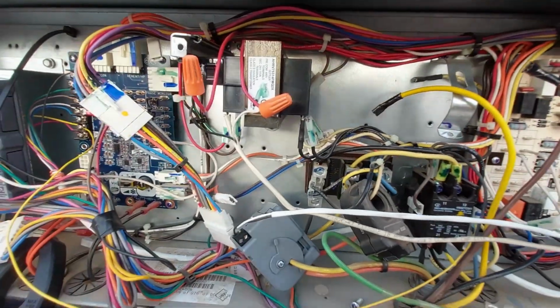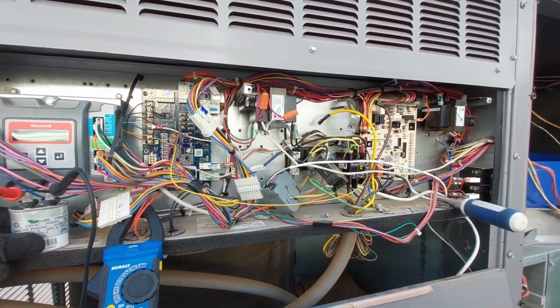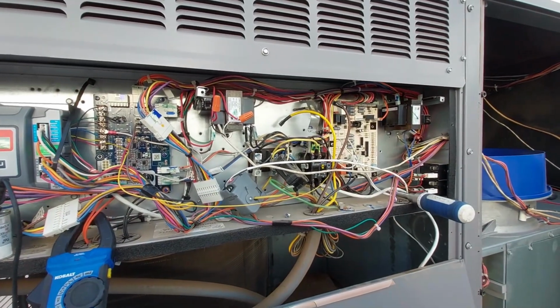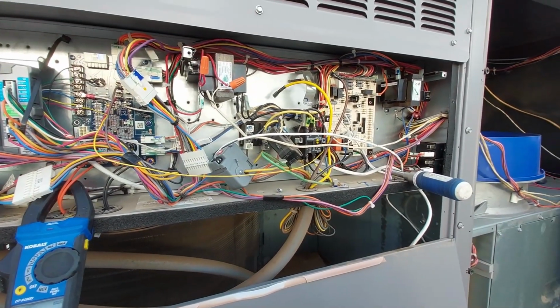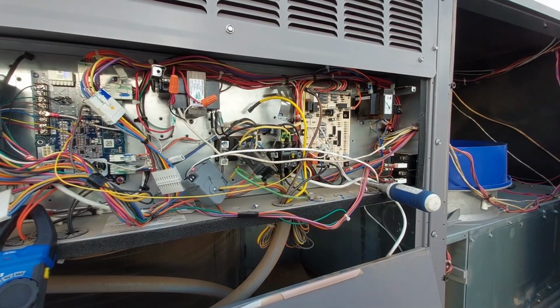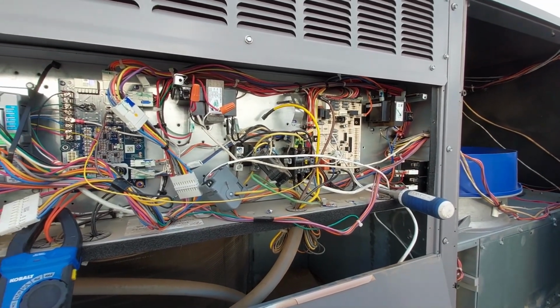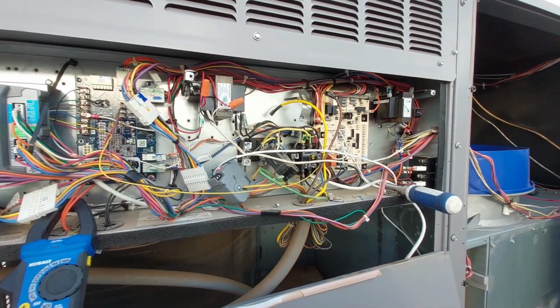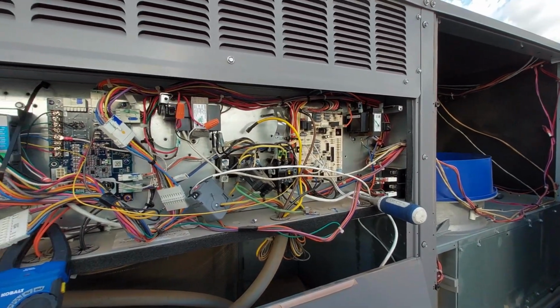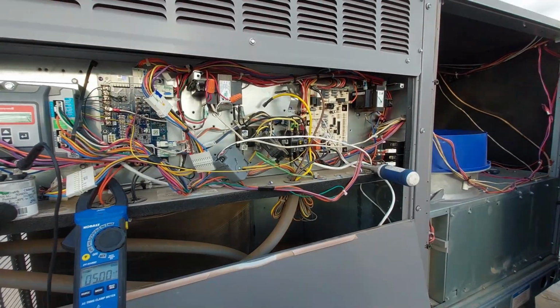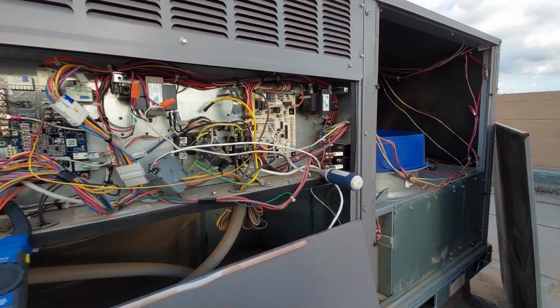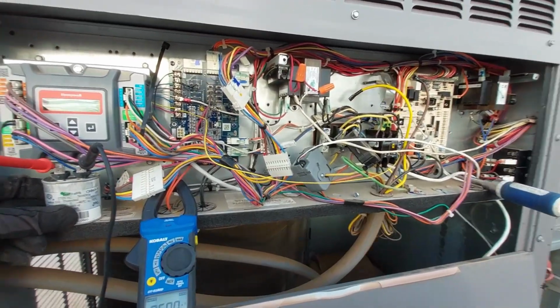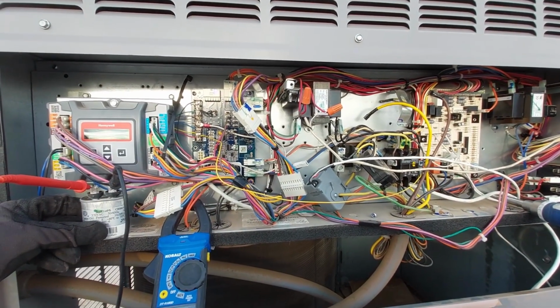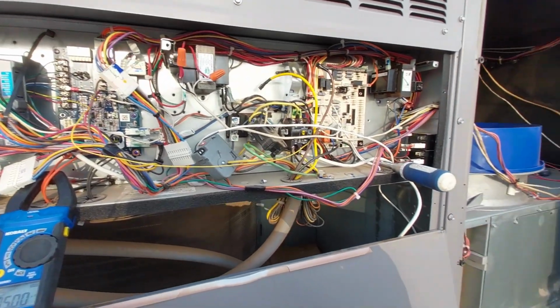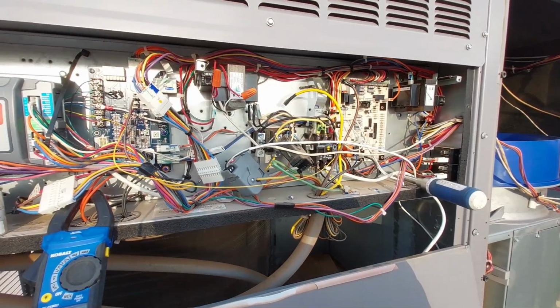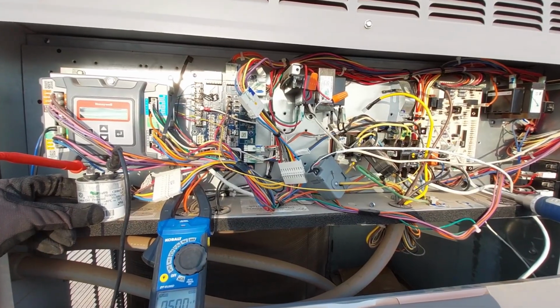So I think this is where I'm gonna call it. I'm gonna try to switch out that condenser fan motor without cutting any wires, just in case that's not the issue. And if it's not the issue, then I'll just put the old one back on and keep diagnosing. But for now, I have to run to the shop, grab a condenser fan motor, come and install it, and go from there. But maybe you guys can tell me what you think is wrong with this unit. To be honest, I'm not the best person at diagnosing, but I try.